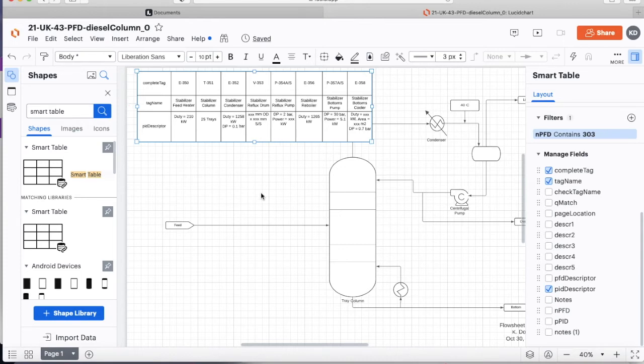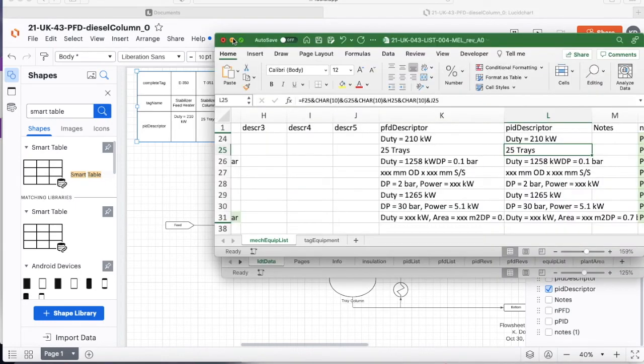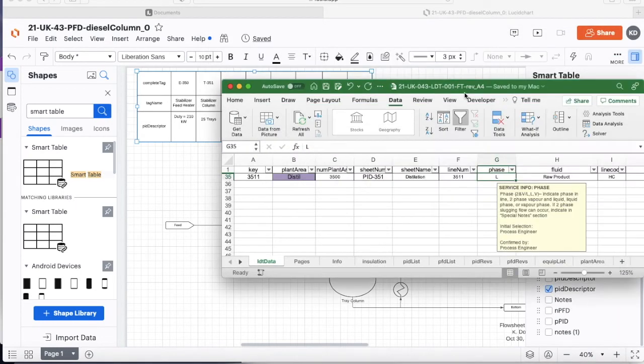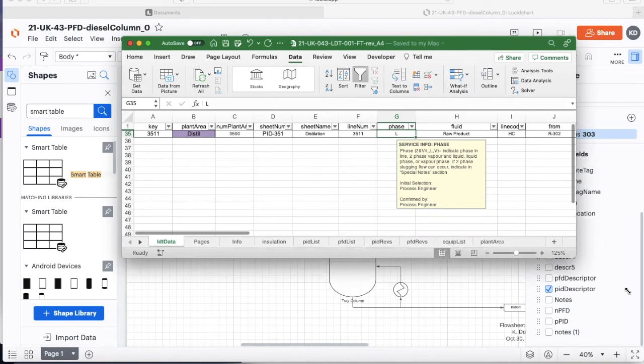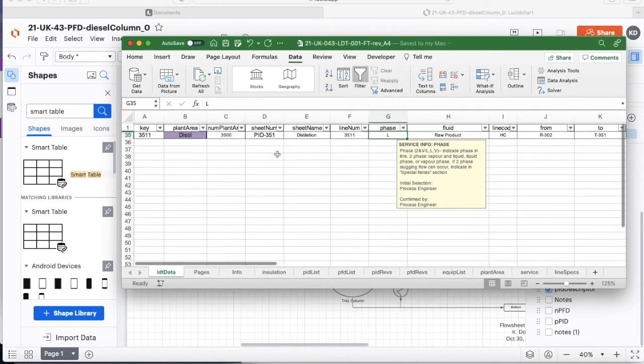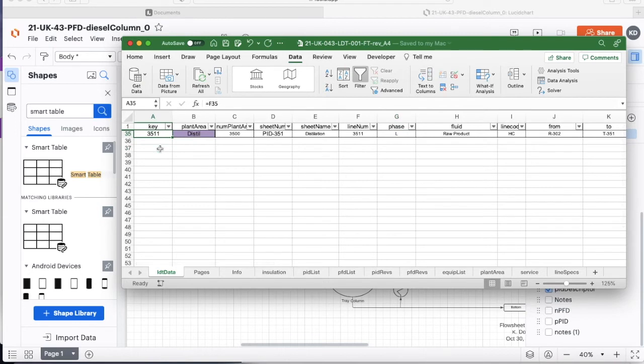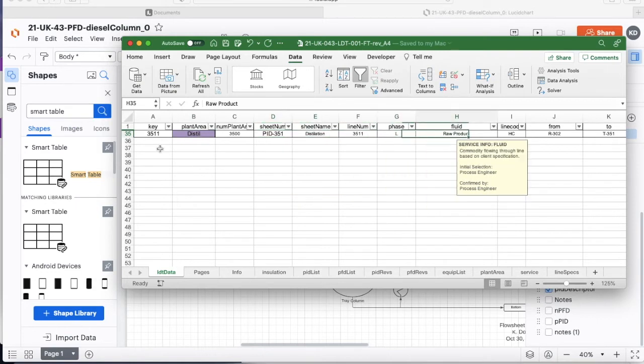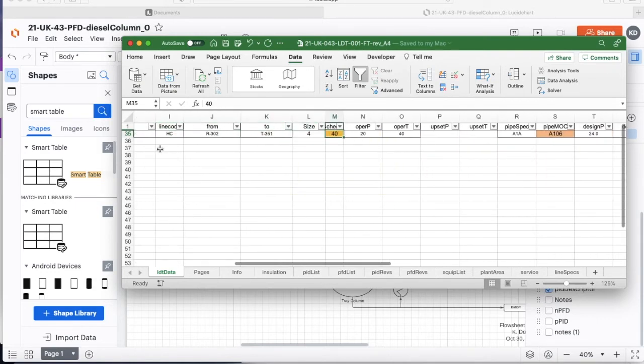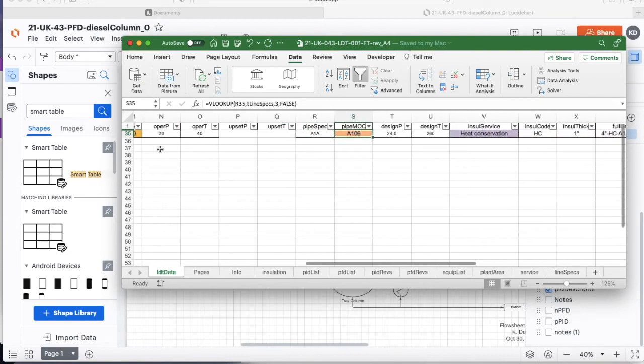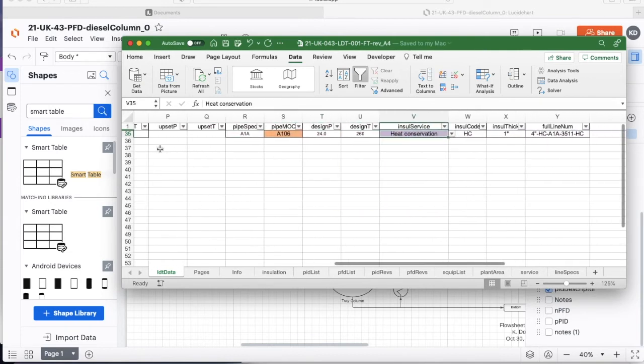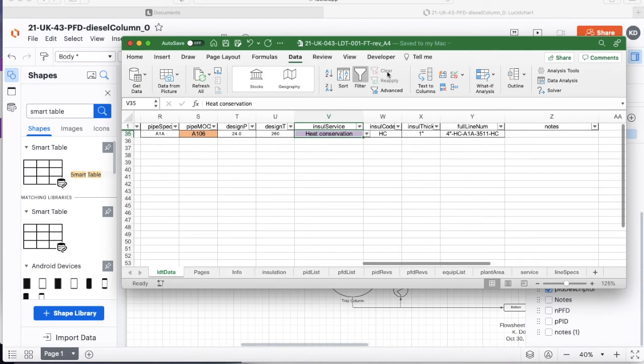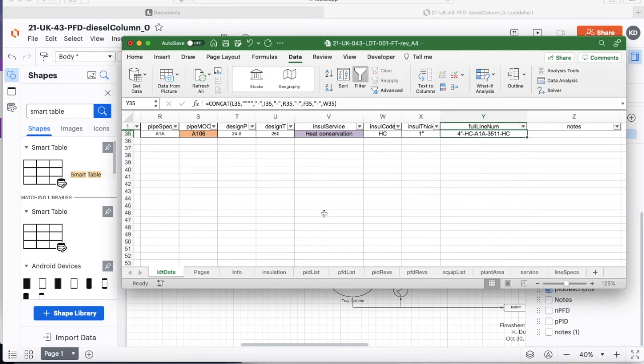Okay. The next thing we're going to do is we're going to work with a line number. And for this we look at a line designation table. And our line designation table probably looks something like this. And I've got all of my other lines hidden. So we only need to look at one. So this is line number 3511. It's in the distillation area. Tons of information about this particular line. We've got materials of construction, design conditions, insulation. And at the very end of the day we have a complete line number. And I want to put that complete line number on the drawing. So let's see how we do it.